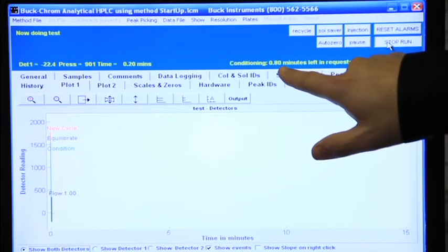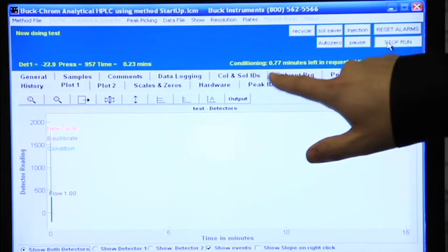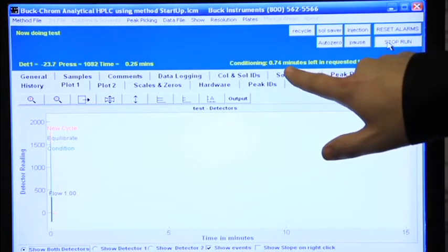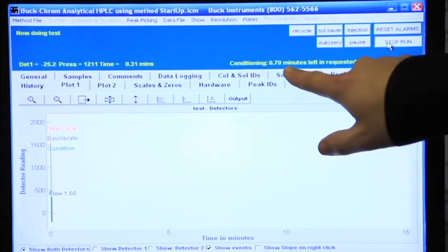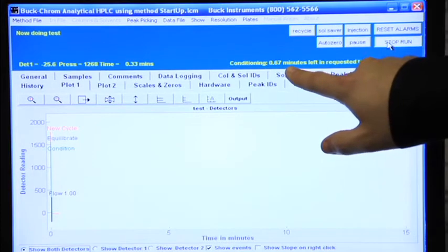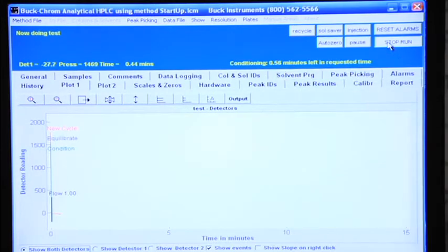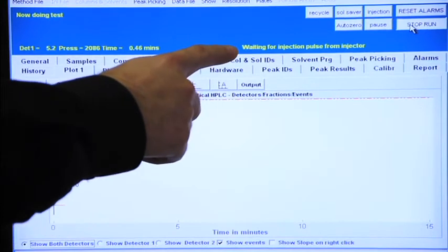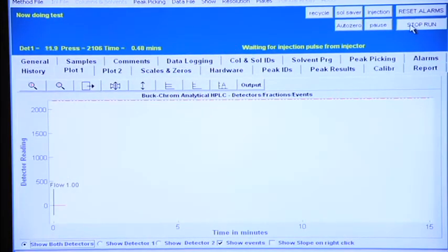You'll see that the conditioning time is actually counting down here. It's going to go for 1 minute. When that minute has passed, it will ask you for an injection signal. When the conditioning time is up, a message will appear that says waiting for injection pulse from injector.